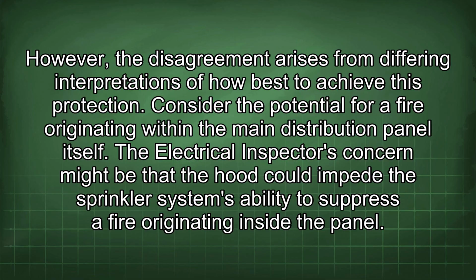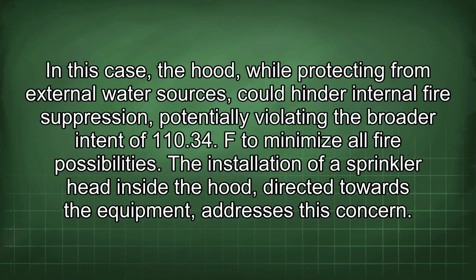Consider the potential for a fire originating within the main distribution panel itself. The electrical inspector's concern might be that the hood could impede the sprinkler system's ability to suppress a fire originating inside the panel. In this case, the hood, while protecting from external water sources, could hinder internal fire suppression, potentially violating the broader intent of 110.34.F to minimize all fire possibilities.